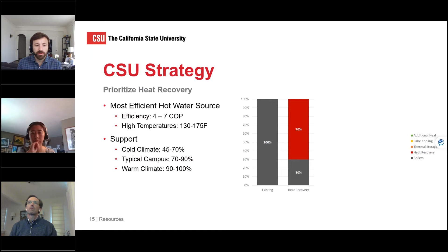The next is to optimize around thermal energy storage and false cooling. Thermal energy storage includes chilled water, heating hot water, and also strategies around domestic hot water. Can we upsize storage tanks to shift loads? Can we use swimming pools if there's a recreation center, and change the schedule of when heat exchangers or heat pumps operate to shift loads when we have excess cooling? And then also optimizing with economizer false cooling, which is a strategy of capturing waste heat from buildings through the chilled water system and repurposing that to be hot water. With those strategies, we can reduce the reliance on existing boilers. Thermal energy storage and false cooling for most campuses can provide around 20 to 25% of additional heating demands on the campus.